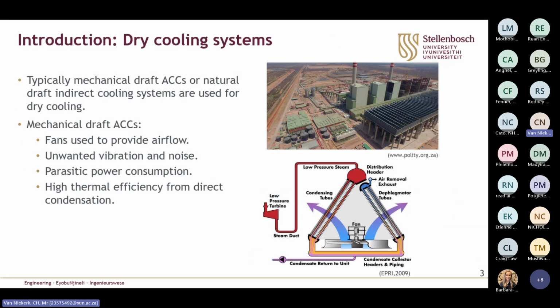Dry cooling generally consists of either mechanical draft ACCs or natural draft indirect dry cooling technologies, where mechanical draft ACCs use multiple large diameter axial flow fans to drive air across the condensing tubes. However, these drivetrains generate quite a bit of unwanted noise and vibrations, leading to regular maintenance and inspections, which increases the downtime and operational cost of the power plant.